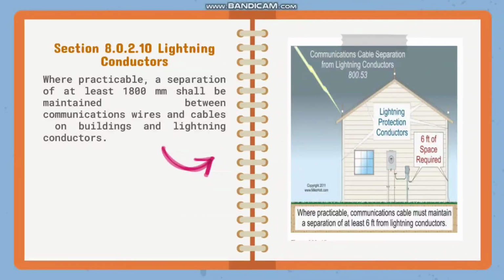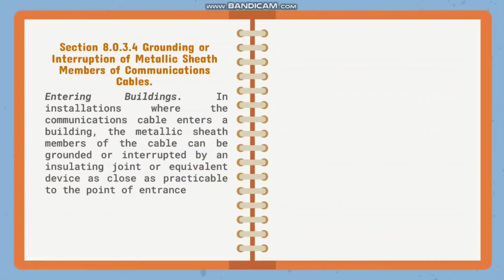So, yung lightning conductors po pala ay isang metal rod na nakamount sa structure para protektahan po yung structure in case po ng lightning strike. Next naman po is section 8.0.3.4, grounding or interruption of metallic sheath members of communications cables. Entering buildings, in installations where the communications cable enters a building, the metallic sheath members of the cable can be grounded or interrupted by an insulating joint or equivalent device as close as practicable to the point of entrance.